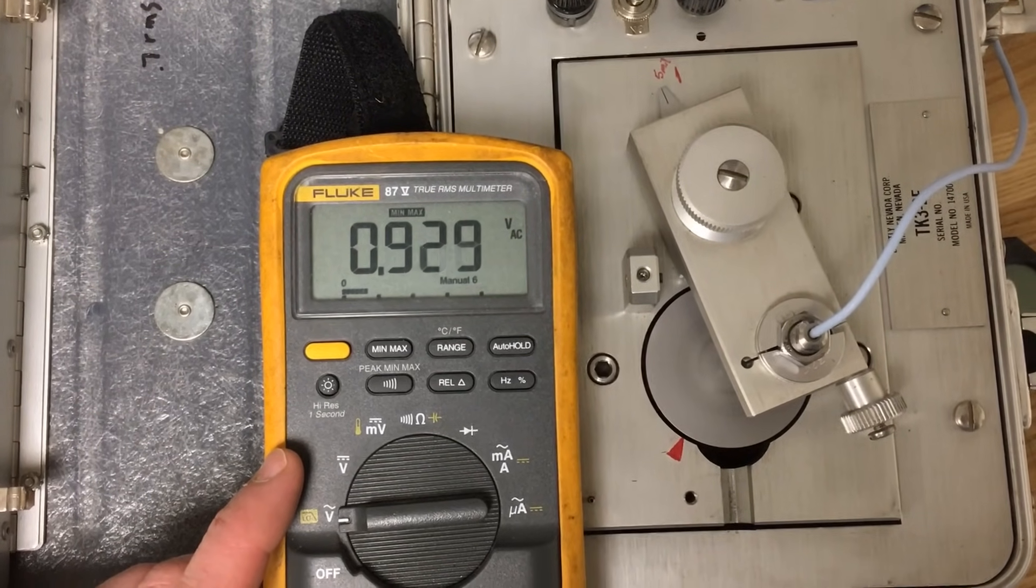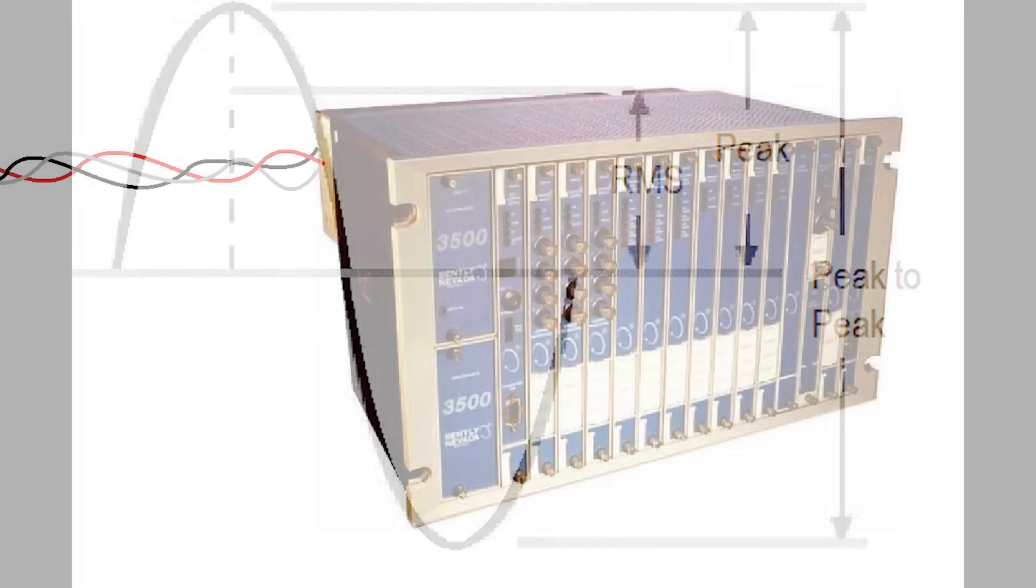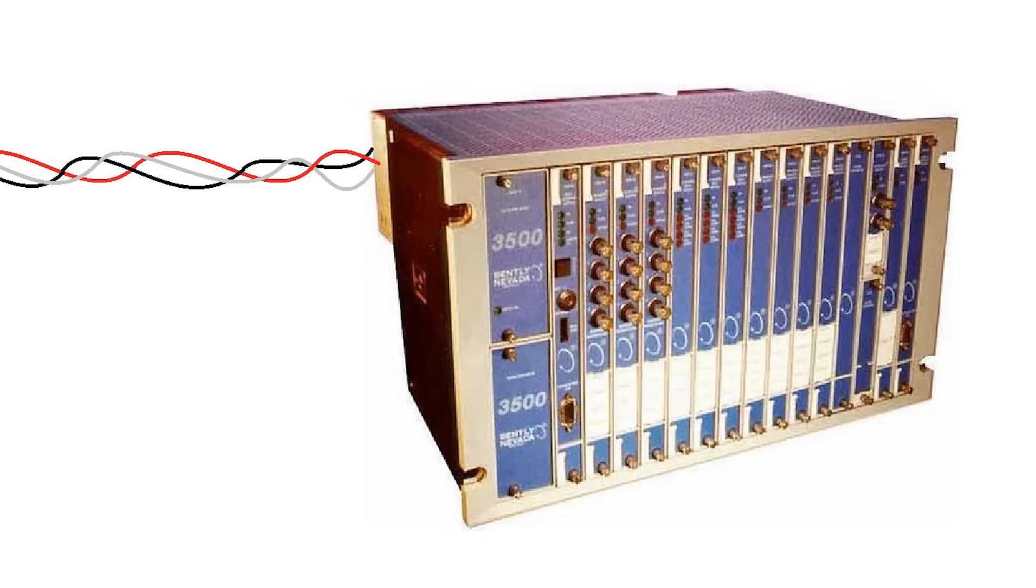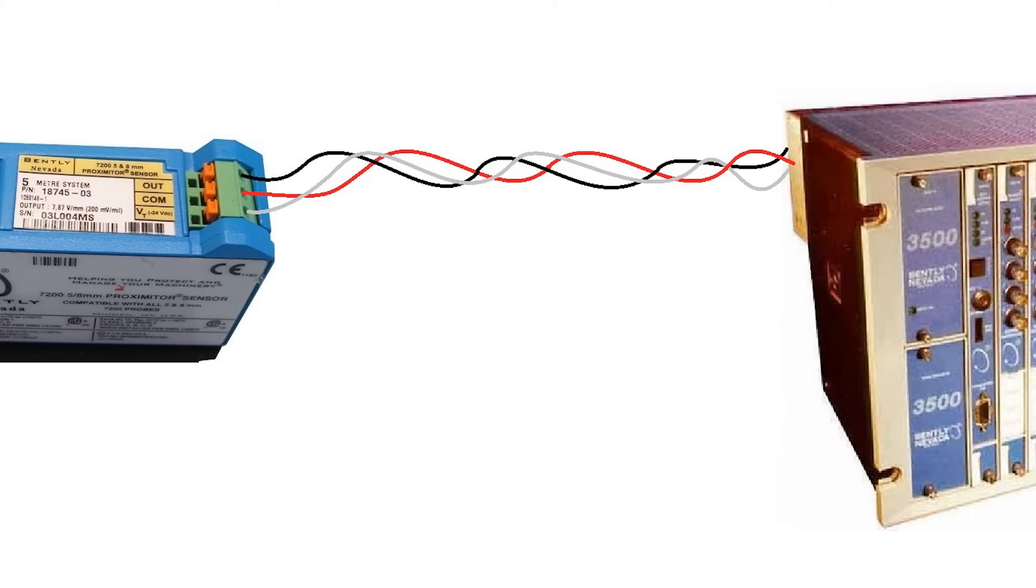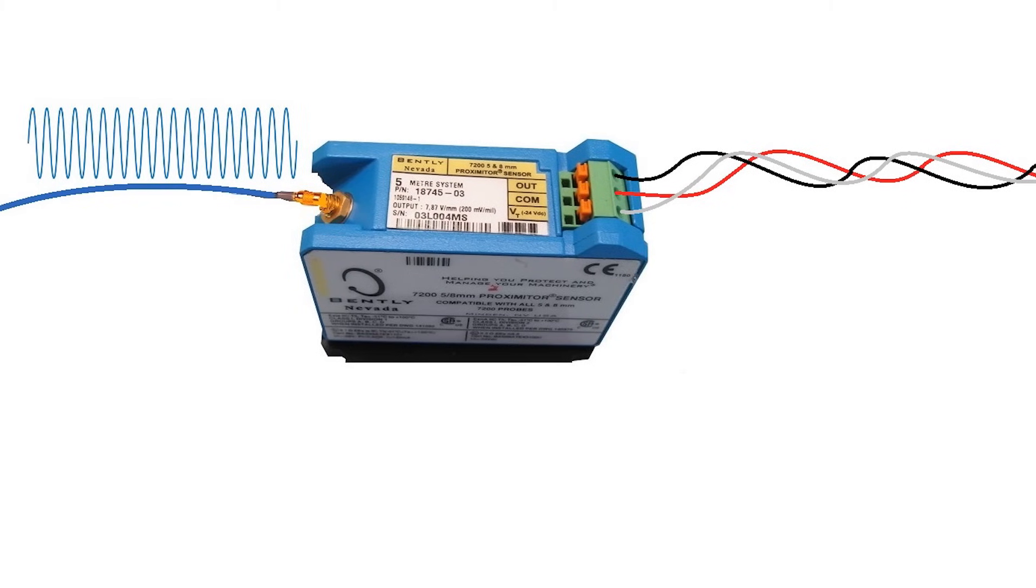However, due to the manner in which a basic voltmeter captures AC measurements, some math needs to be used to convert this to a usable vibration measurement. This process will be covered in a later video during the dynamic test demonstration. The proximity monitoring card, which is connected to the output voltage terminals of the proximitor, will automatically convert this AC voltage to a total shaft travel value in the unit of mils.